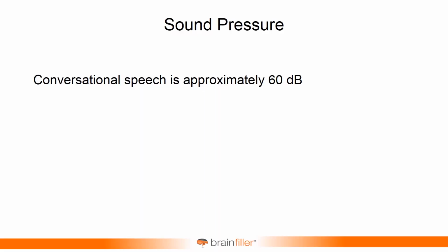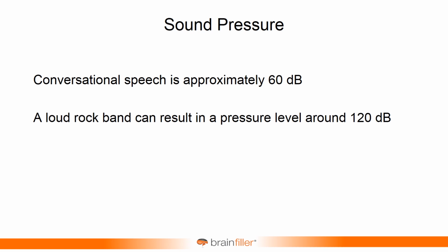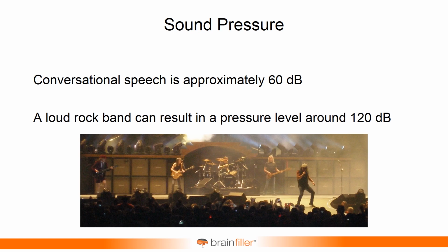The sound pressure. So hearing protection, I think, as most people know, is required, at least according to NFPA 70E. And the sound pressure could be absolutely staggering. As a frame of reference, conversational speech is approximately 60 dB. dB, decibels, that's the measurement that we use for sound pressure. This is actually sound pressure. And you take this up to 120 dB, and that's like a very loud rock band.